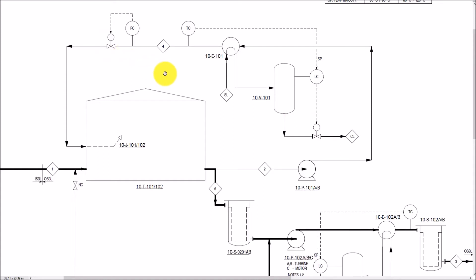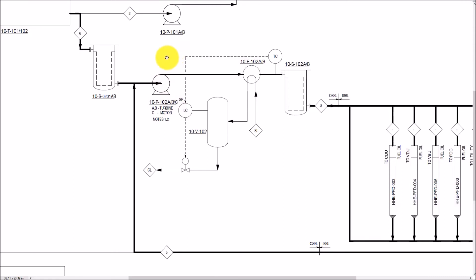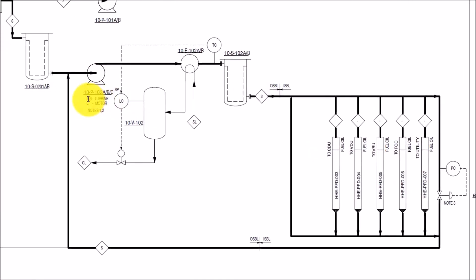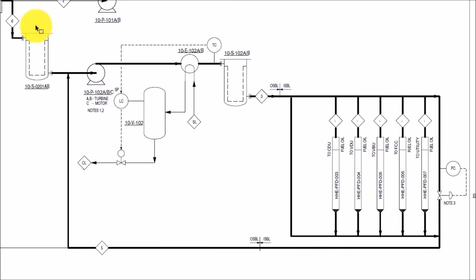It can be hydraulic, pneumatic, or motor operated type. See this detail of the pump. The recycle pump has a head of 60 meters and the plant fuel oil pump has a head of 216 meters — this must be a huge pump. These pumps are turbine driven, which means these are critical pumps. Turbine-driven pumps are provided where you want to run the pump even if there is a total power failure in your plant. Here we have two basket strainers — one on the suction side and one on the pump discharge side — and a heat exchanger to maintain the temperature of the fuel oil. The suction strainer will protect the pump impeller from any foreign object that can damage the pump, and the discharge strainer will ensure clean supply to the user unit.